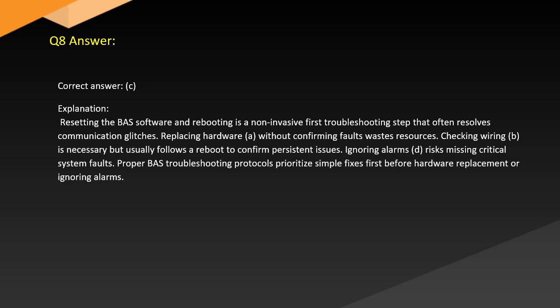Answer. Correct answer: C. Explanation. Resetting the BAS software and rebooting is a non-invasive first troubleshooting step that often resolves communication glitches. Replacing hardware without confirming faults wastes resources. Checking wiring (B) is necessary but usually follows a reboot to confirm persistent issues. Ignoring alarms (D) risks missing critical system faults. Proper BAS troubleshooting protocols prioritize simple fixes before hardware replacement or ignoring alarms.